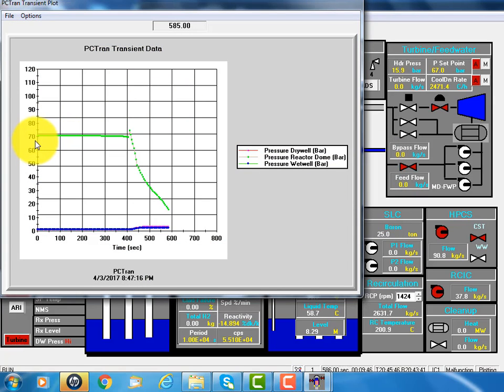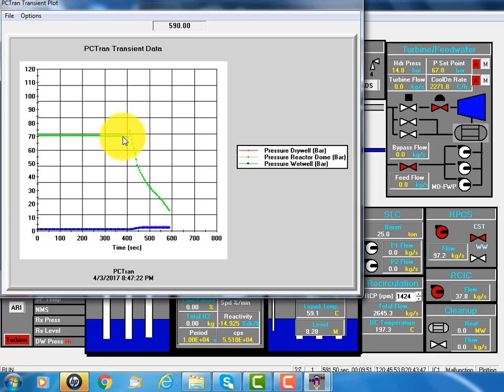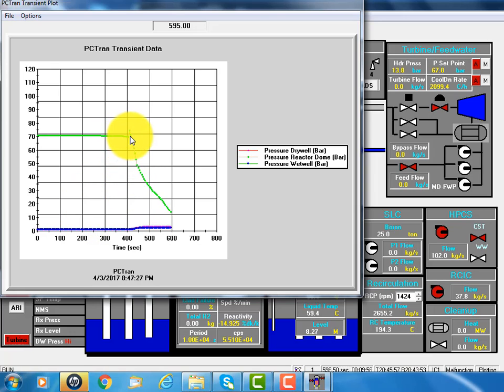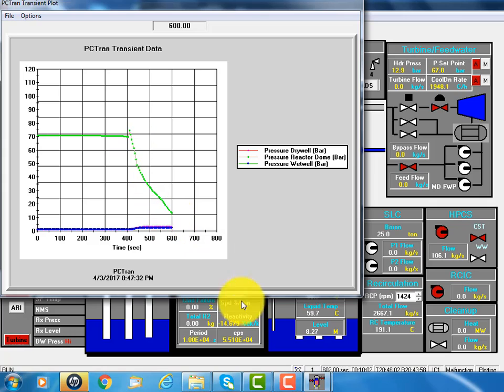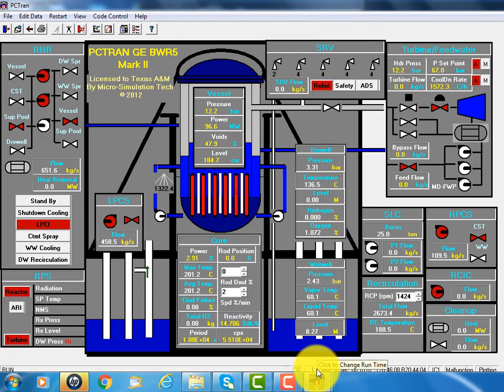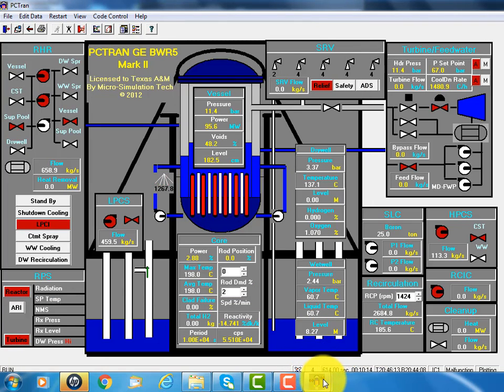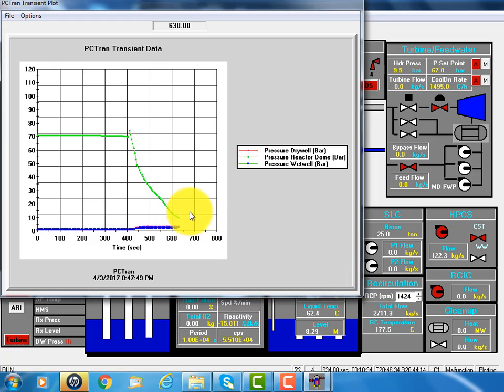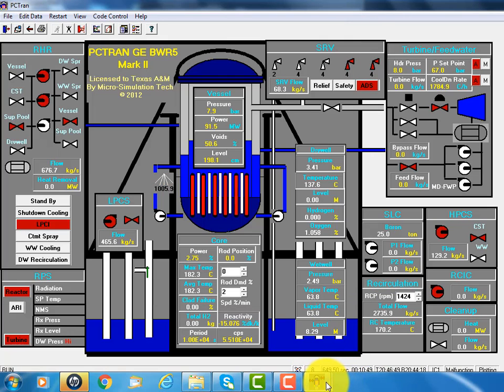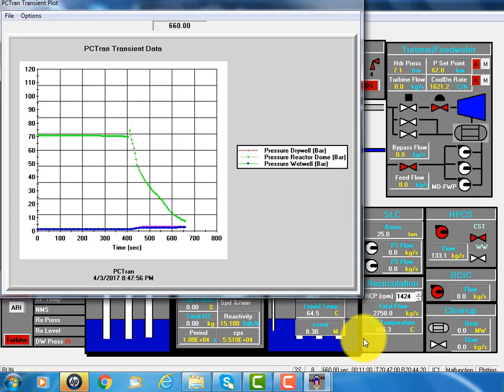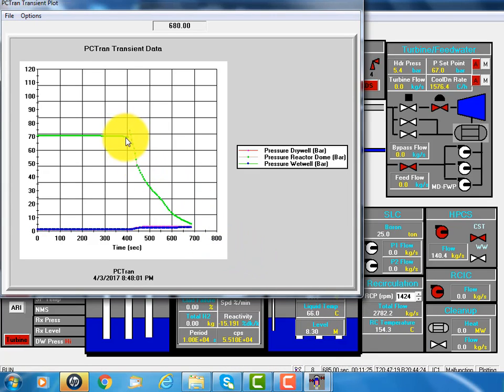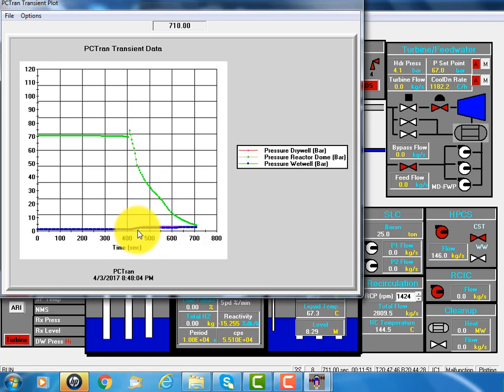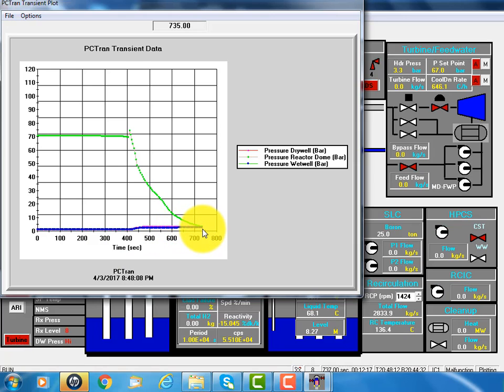You see, the light green line, the reactor pressure, 70 bar or 1,000 psi. At the start of the accident pipe break, it drops dramatically. And now we are simulating the curves are still moving. Let's accelerate it to four times faster. You see, or even eight times faster. See, the reactor vessel pressure goes down, and the containment dry well and suppression pool pressure will go up. And then eventually become the same, equalized to each other.